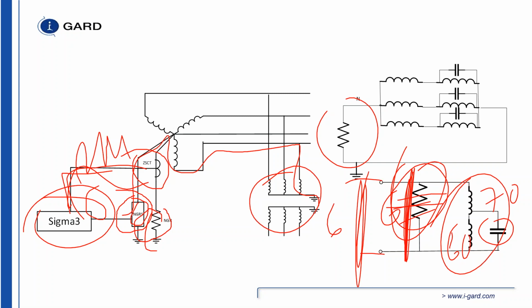Okay. What if the NGR is coupled via a zigzag auto transformer? You know, funny you should mention that. We've implemented a couple of those, and we've had issues with it, but we've worked around it, and we found a solution for that, because unfortunately the zigzag transformer is very low impedance when it comes to zero sequence currents. So we have had issues with that in the past, but we did find a solution that works well with that type of application.